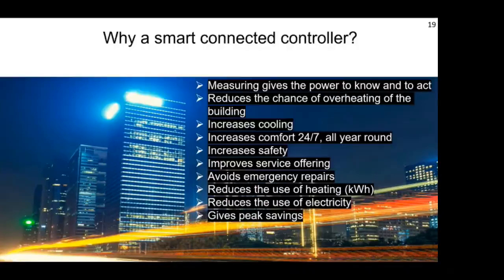We can then do this automatically, via whichever system you've got set up. Because the changes are small and can be implemented anytime, they minimise the impact for occupants. If you look at a government building, and I live in South Wales, if you go past the DVLA, the lights are on 24 hours a day and no doubt the heating's going on. But if you use the building controller and you know at 9 o'clock that everybody's gone home, you could turn the system down a couple of degrees. That makes the system more efficient. Just imagine, in central Birmingham business district, how many buildings are running 24 hours a day, 7 days a week with the heating turned on. Whereas with the building controller, you could actually turn it down via your heat station.